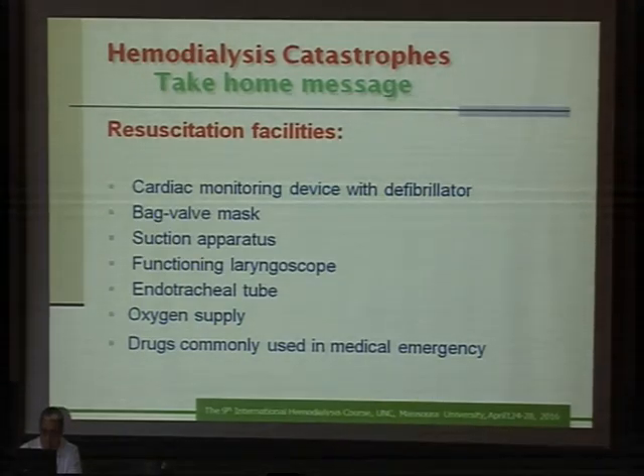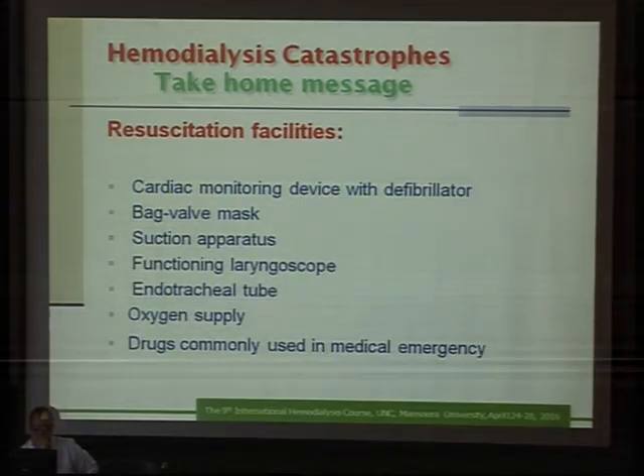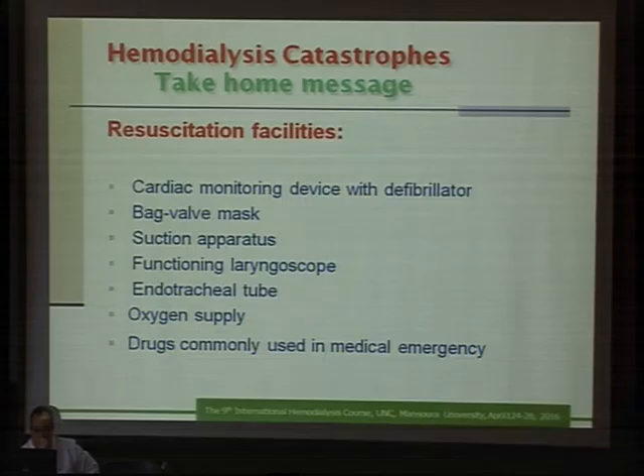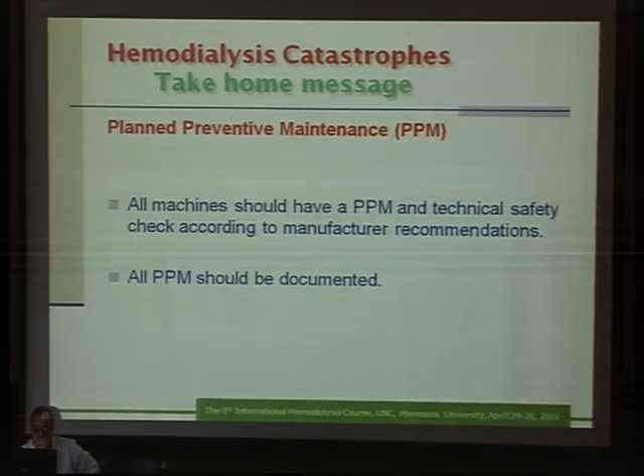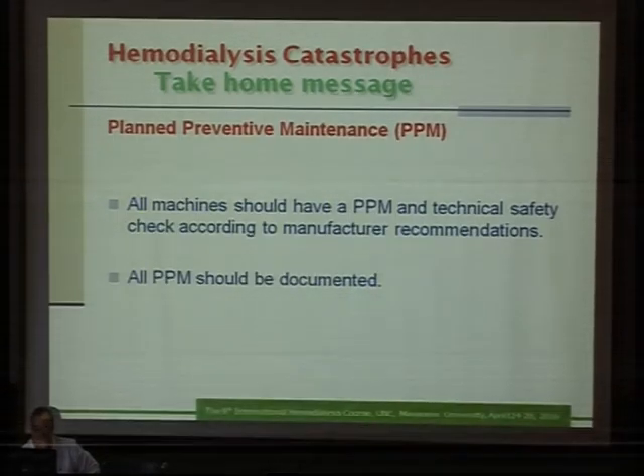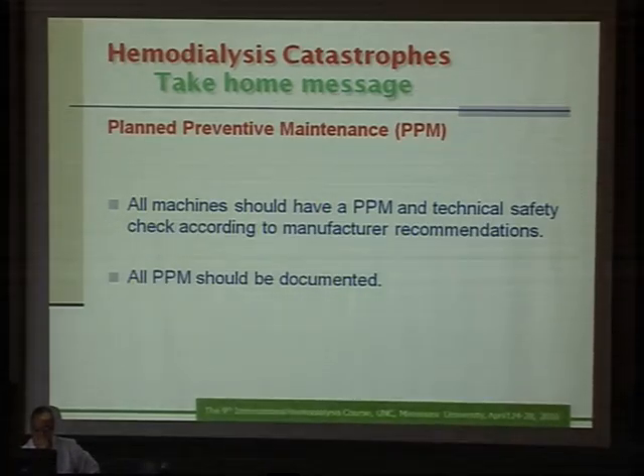The take-home message: resuscitation facilities — including cardiac monitoring devices, defibrillator, bag-mask, suction apparatus, laryngoscope, endotracheal tube, oxygen supply, and emergency drugs — together with trained staff, should be available in the dialysis unit. All machines should have a planned preventive maintenance schedule and technical safety checks according to manufacturer recommendations. Each dialysis unit should have its own manual and guidelines that are strictly followed.